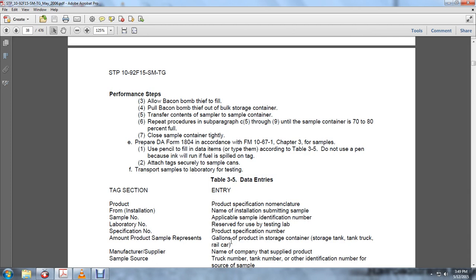Prepare the DA Form 1804 according to Field Manual 10-67-1, Chapter 3, Samples. Use a pencil to fill in the data items or type according to Table 3-5. Do not use pen, because the ink will run in fuel and spill on the tag. Attach the tags securely to the sample cans. Transfer the samples to the laboratory for testing.